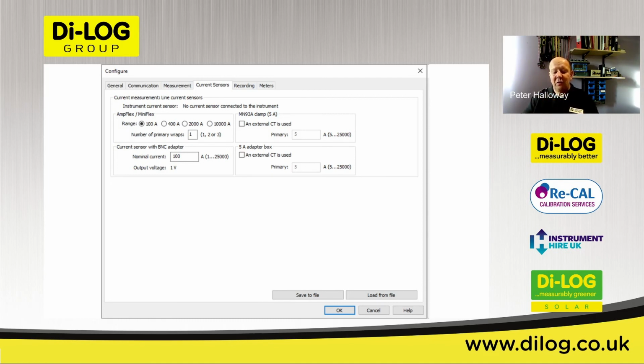This is a bit like a transformer, isn't it? Your conductor is the primary, this is the secondary, so you've changed the transformation ratio now by putting a wrap on there. If you do that, you have to tell the software that you've done it. So by default it's 1, but if you put a wrap on there, you'd change it to 2. So that's where you do that.